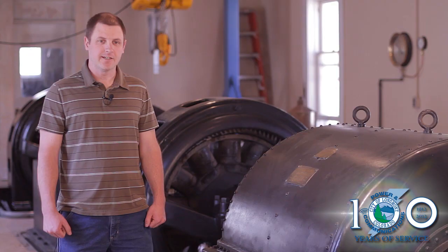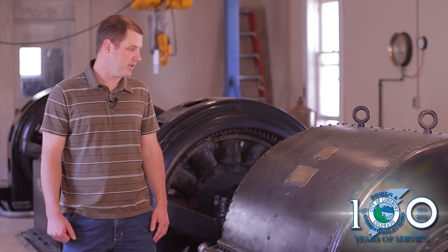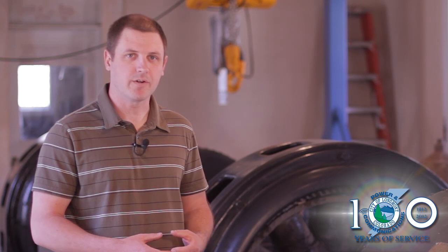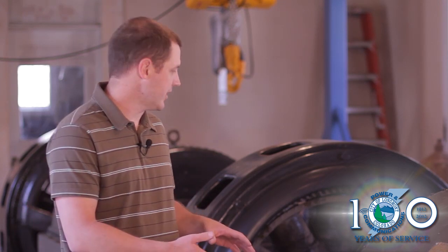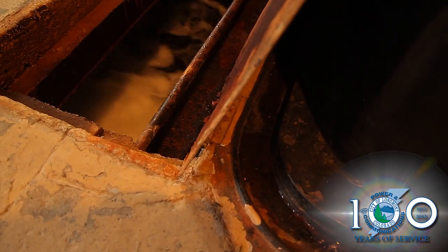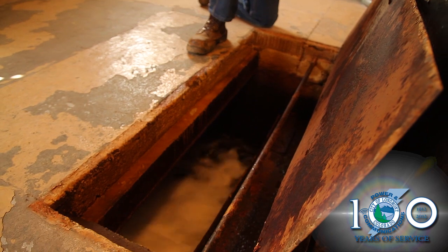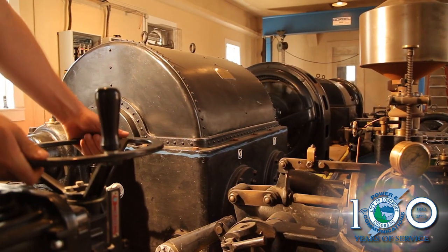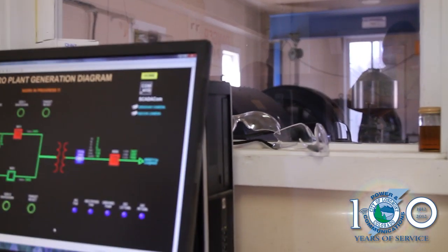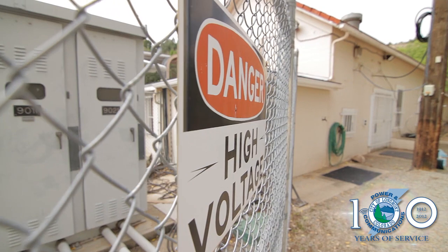There are two electrical generators and two turbines. I'm standing here inside of Longmont's hydroelectric plant next to the Pelton turbine, one of two turbines we use to generate electricity. We want to take that high-pressure, high-flow water source and turn that into mechanical energy with the turbine. It's no different than a water wheel or spraying a garden hose on your bike tire — when you spray water at an object, it's going to make it move or turn as a turbine does. That rotational energy is then transferred to the shaft of the electrical generator, and we spin that shaft at the right speed to put the right voltage and frequency out, so we can match that to our existing distribution grid and push that power back to the residents of Longmont.